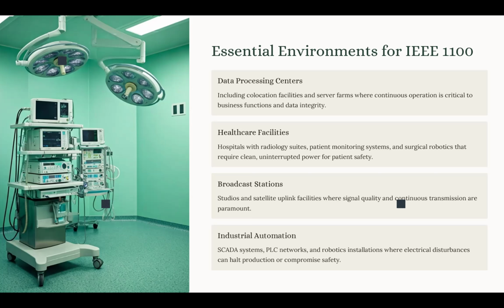So we need to follow some practices recommended in IEEE 1100 to make sure we are addressing those problems. For example, IEEE 1100 recommends a hybrid grounding and signal reference grid. We are going to talk about those concepts again in upcoming slides. Or we could provide a redundant power topology, so we make sure we have an ongoing power supply. There is also harmonic control and load segregation. We already talked about those. By using K-rated transformers and harmonic filters, we make sure that the servers with high nonlinear loads don't face any challenges or issues that could jeopardize their functionality.